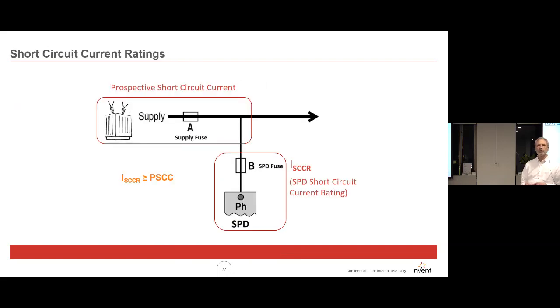This is a bit about fusing. So the fuse to the surge diverter, you don't necessarily have to have a separate fuse going down there. You could just use your supply fuse if it's within the required sizes. For a standard surge diverter, the standard says that 32 amps may be used, and typically up to 100 amps would be used, so somewhere between 32 and 100.